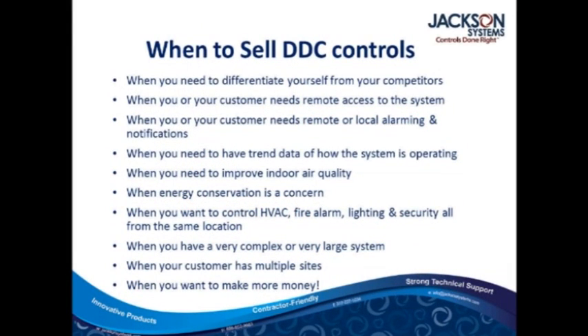But if you have something that's simple like rooftops, if you have 50 rooftops, having a DDC system is a huge help. If you have 50 rooftops in an open warehouse, you probably can't even tell if 10% of them are offline. You have to go up there with gauges and everything else. As you'll see when we take a look here, you can look at the rooftop and say, hey, it shows I got both compressors running. I'm still pumping out 74-degree air. Rooftop number 4 has obviously got a problem. So definitely, if it's large or complex, it's a great reason to have DDC controls in your building.